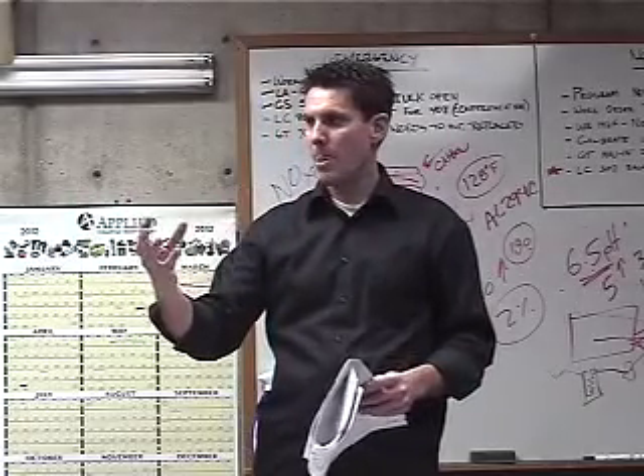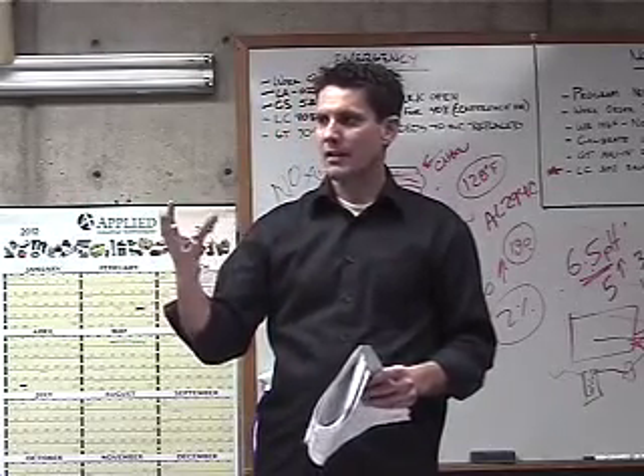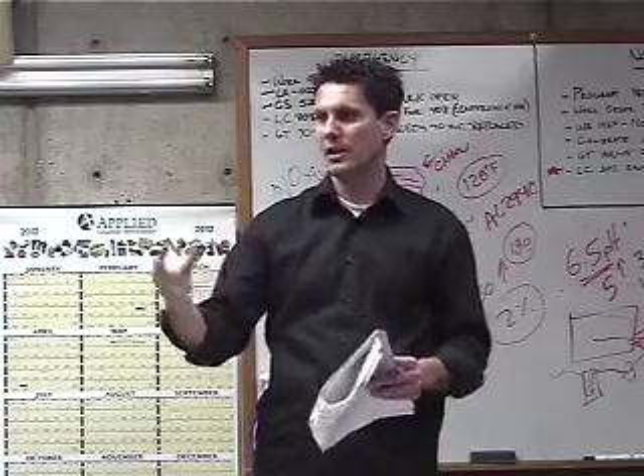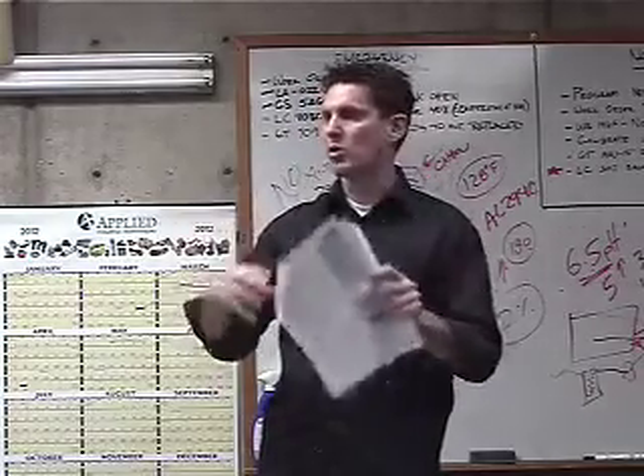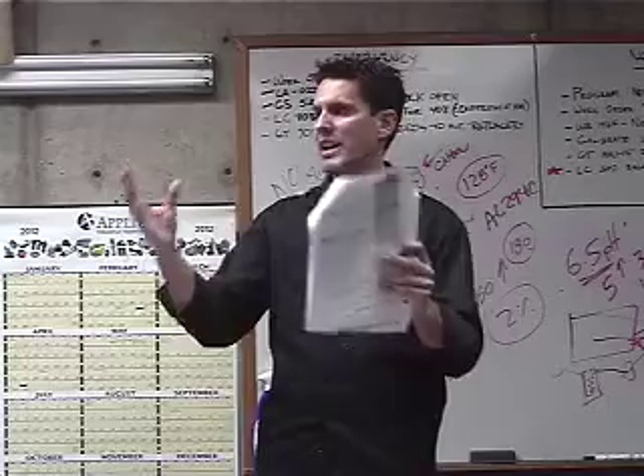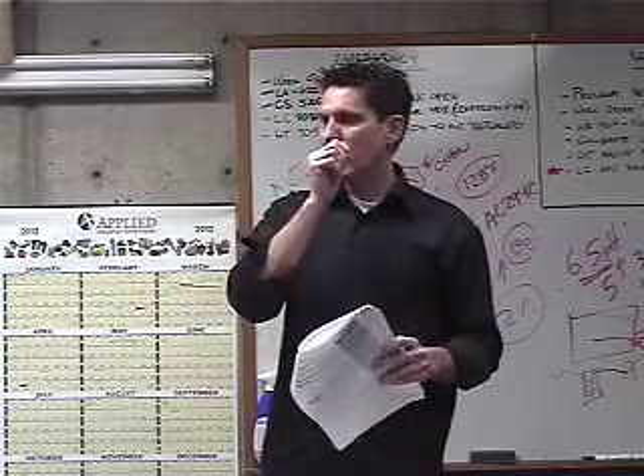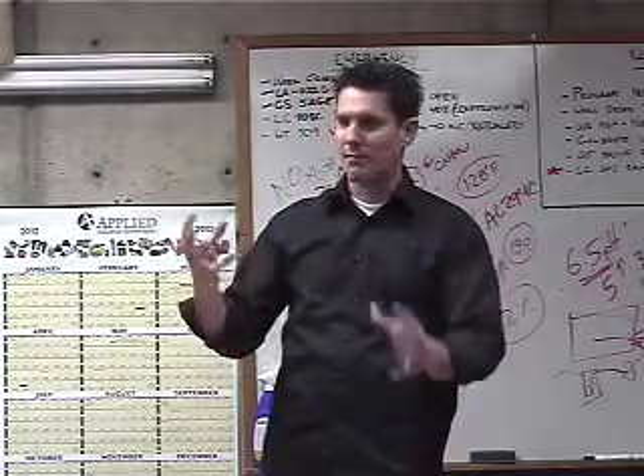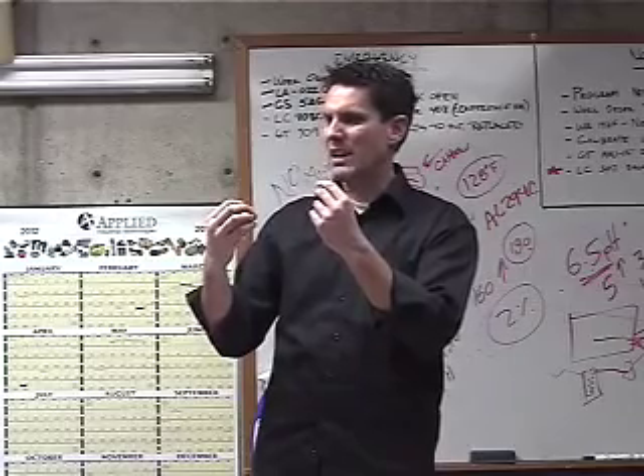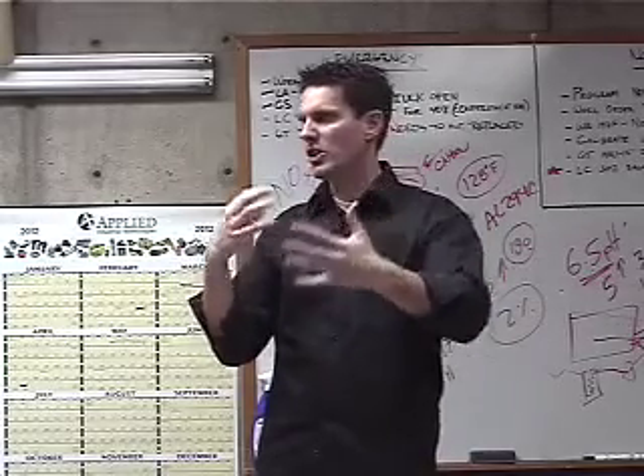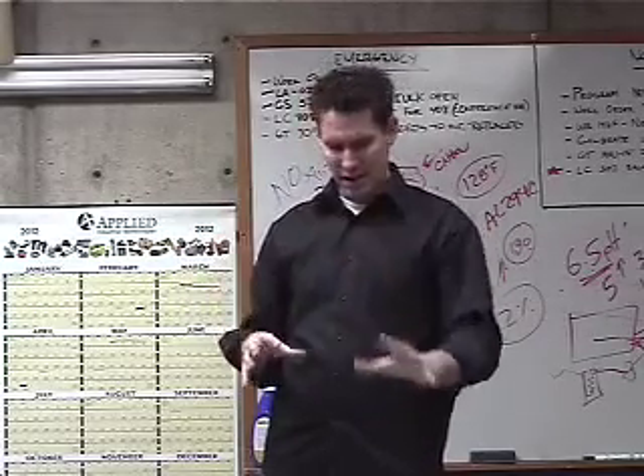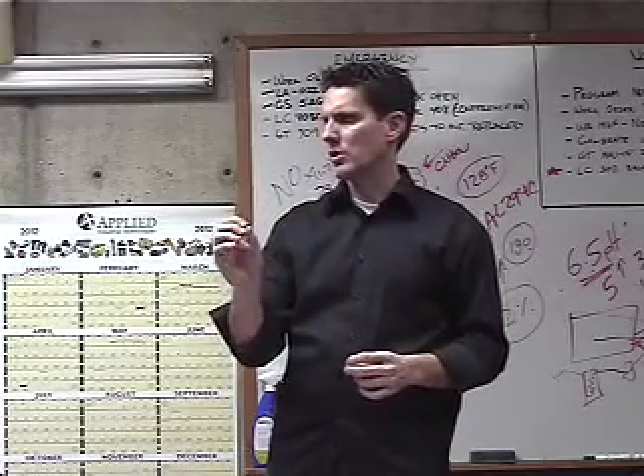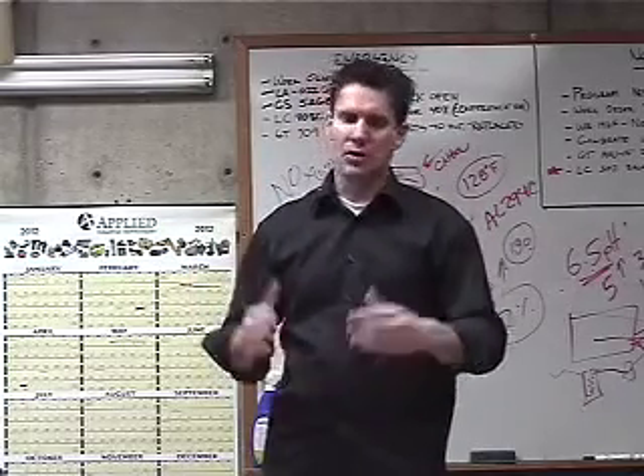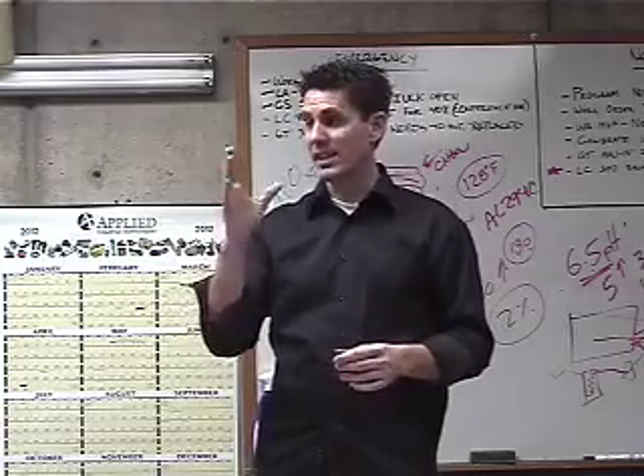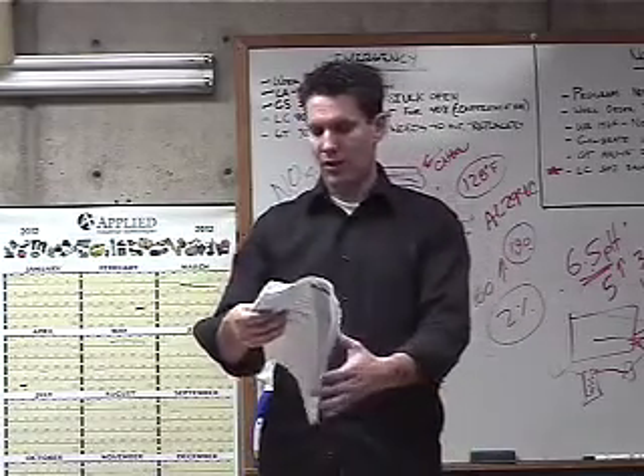High pressure air. Too much air, too much oxygen in there, and it'll be a very brilliant orange, or I'm sorry, very yellowish look. If there's not enough oxygen, the flame might be kind of lagging and it will be a deep orangish look, not a brilliant orange, kind of a dirty orange look. Those are the signs you want to avoid. If you look in and you see that, again, check it weekly. Make sure that it looks good.